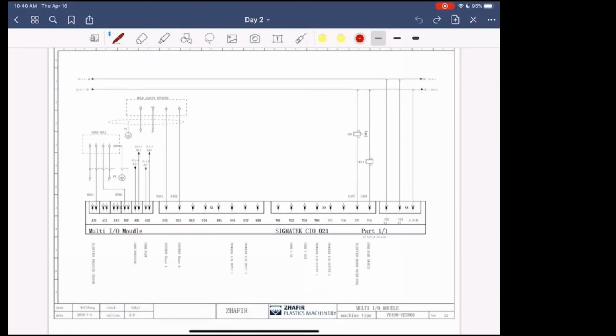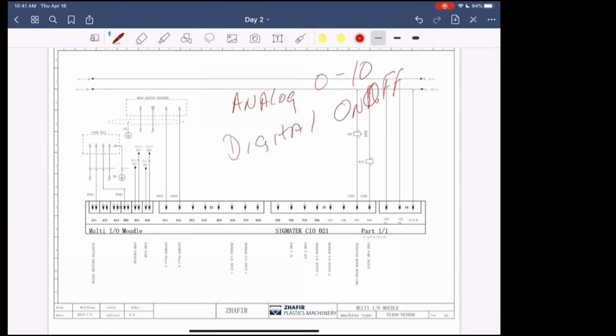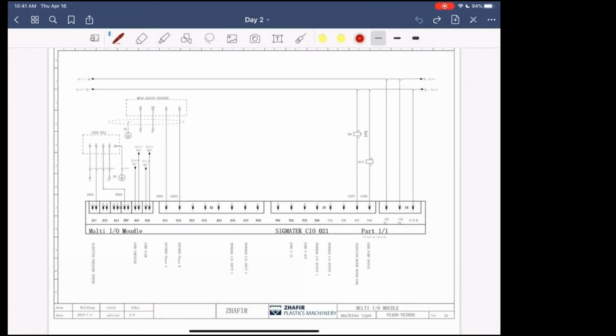There's a multi-IO, which is both analog and digital. And again, the difference between analog and digital: analog is 0 to 10 volts on this machine. Digital is on or off. So a digital signal is just two states, either on or off. An analog signal is a range from 0 to whatever voltage you have. So that's how all the transducers work. They work off of voltage.